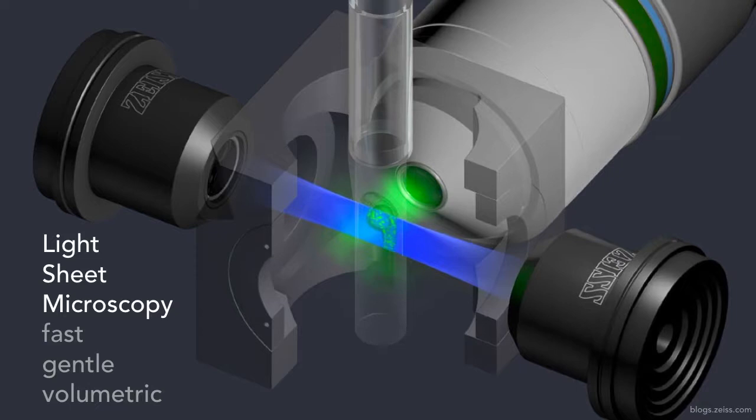So what is light sheet microscopy? Light sheet microscopy is essentially a new modality of imaging. It's almost 15 years old now, but it's a very powerful technique because it lets you observe an entire living system, like a zebrafish larva. The way it works is you generate sheets of light with illumination objectives by scanning a laser beam up and down here, and then we observe the light coming out of this sample, the fluorescence light, because we modify these organisms to be fluorescent.